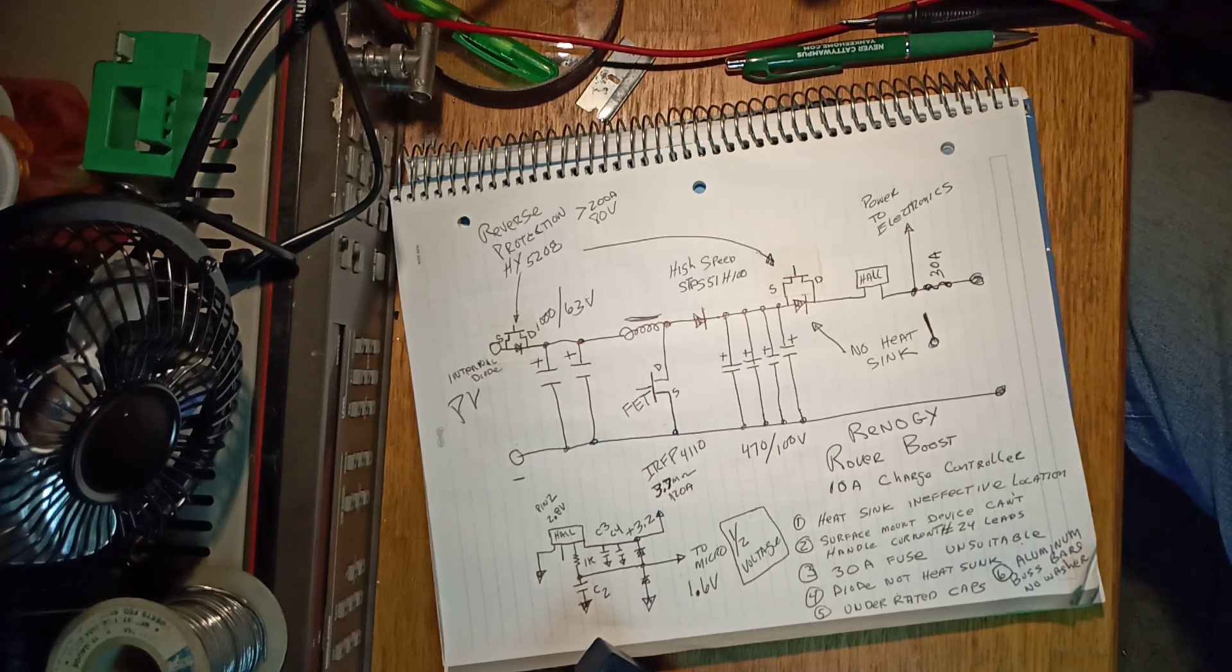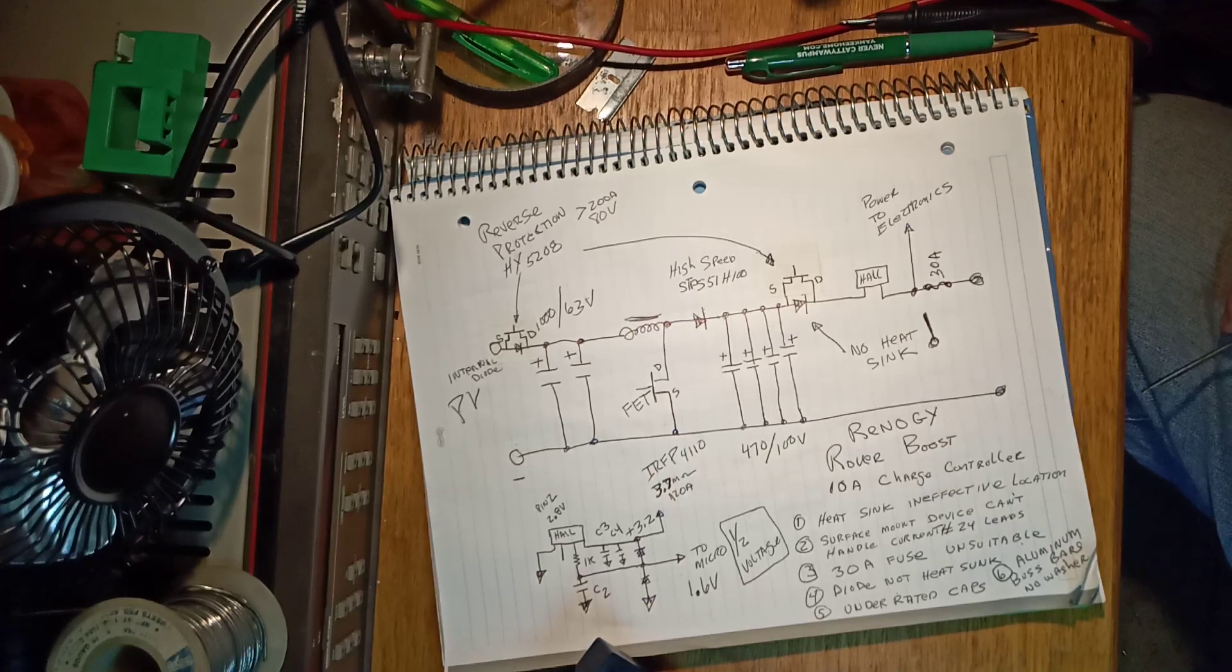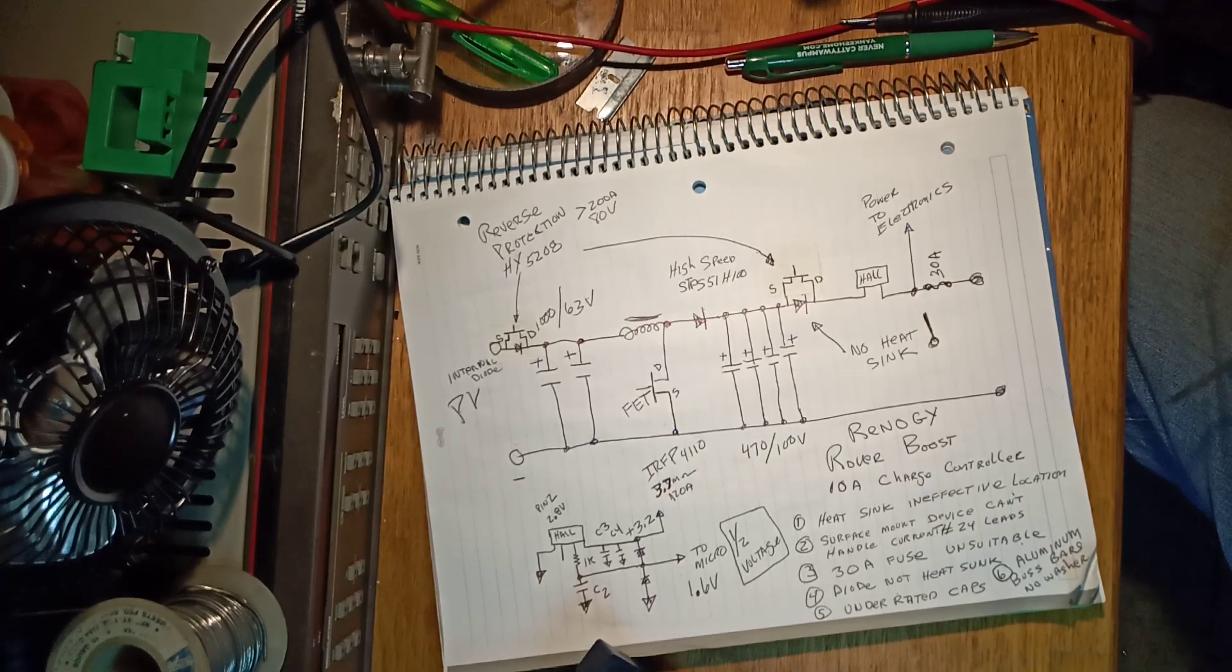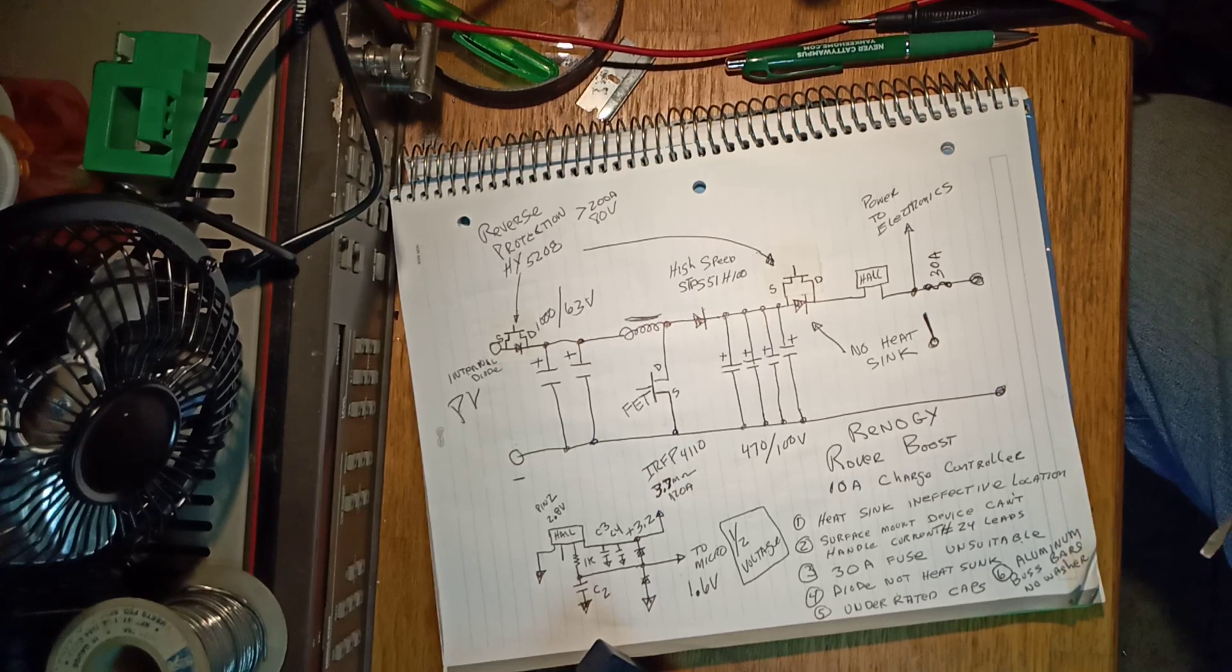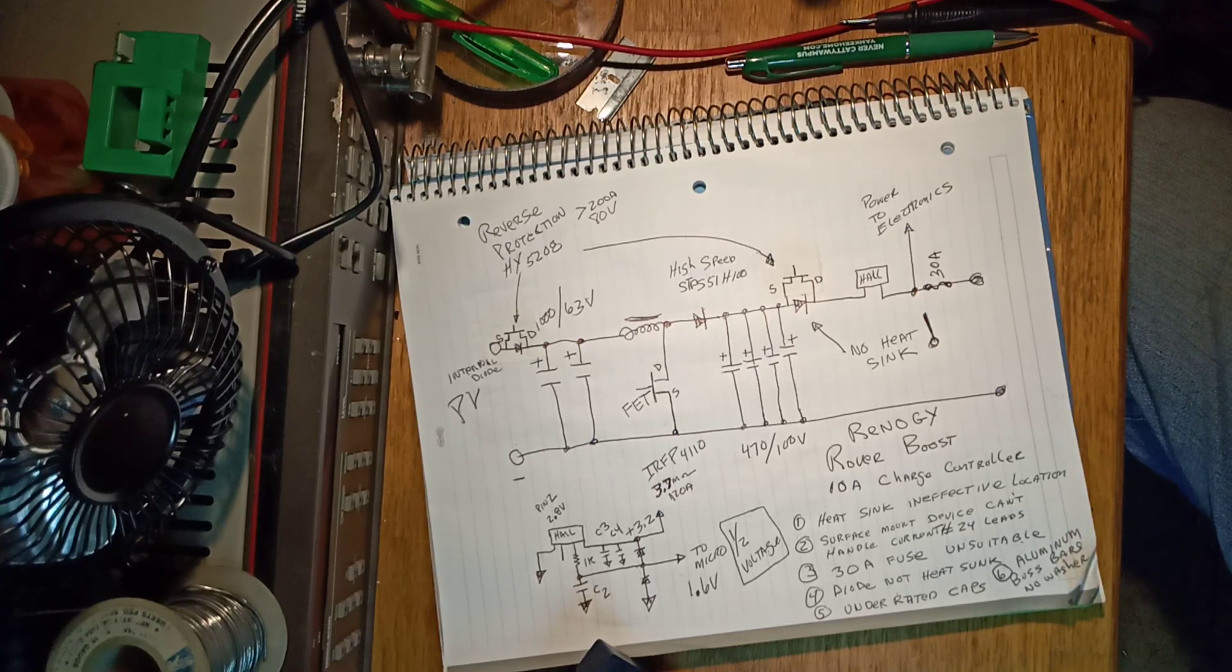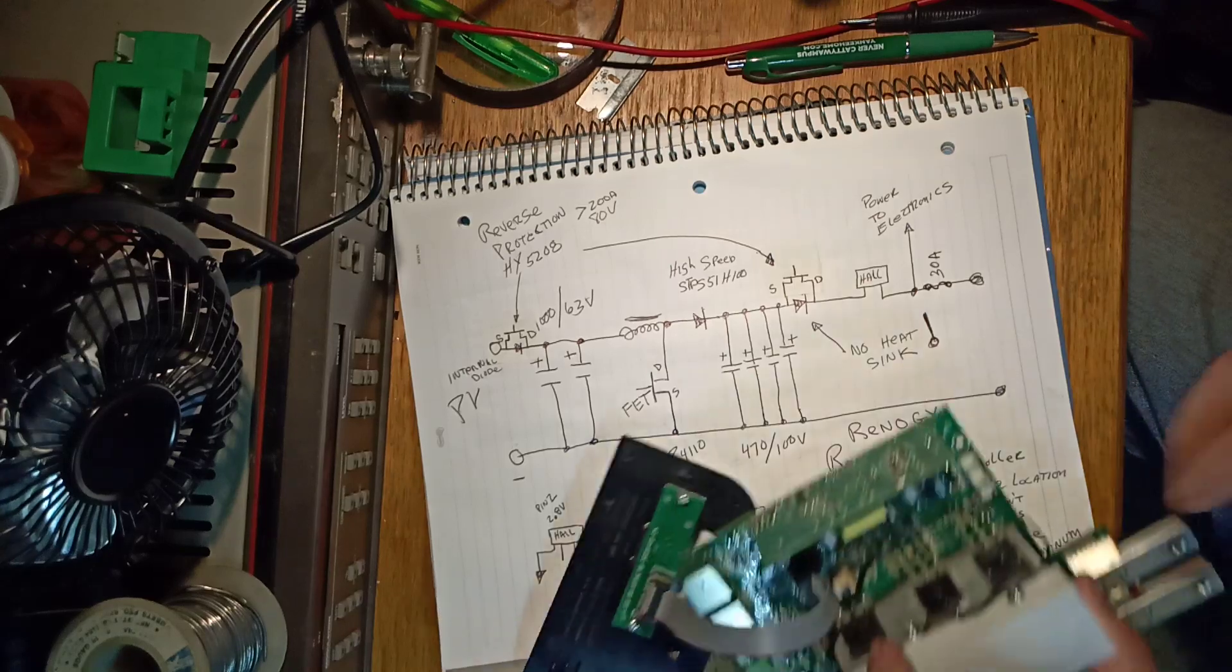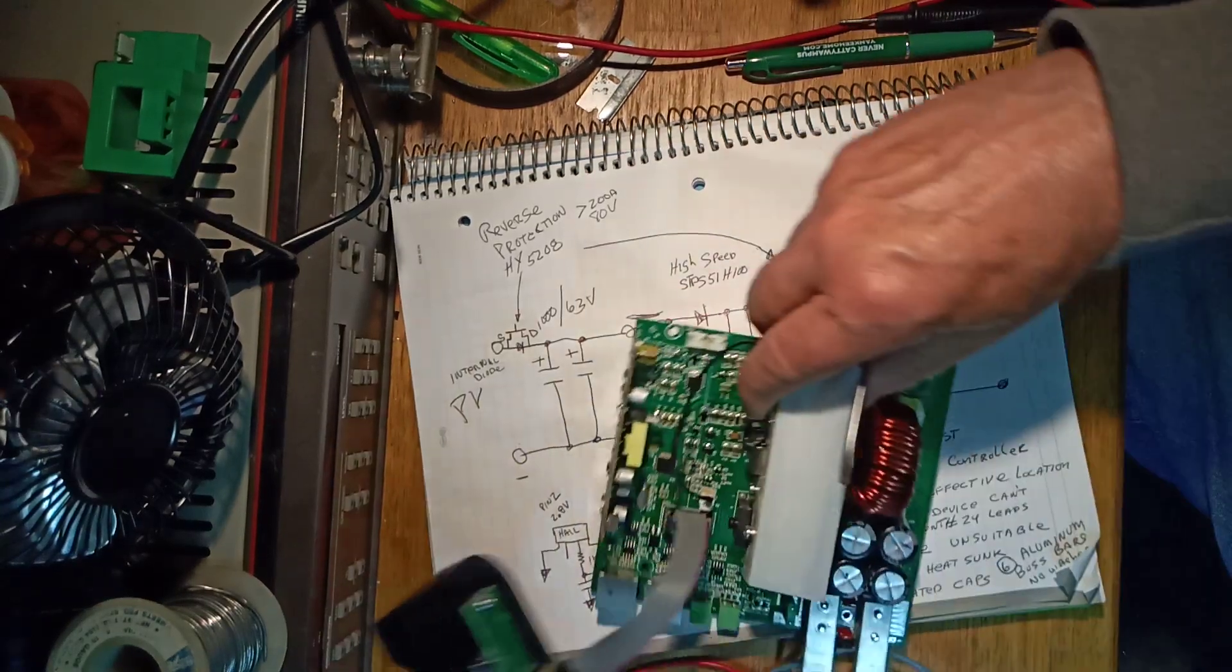And these aluminum bus bars. Aluminum just is not good out in the weather. And it really needs at least some washers with some lock washers on it. So, that's my story and I'm sticking to it.